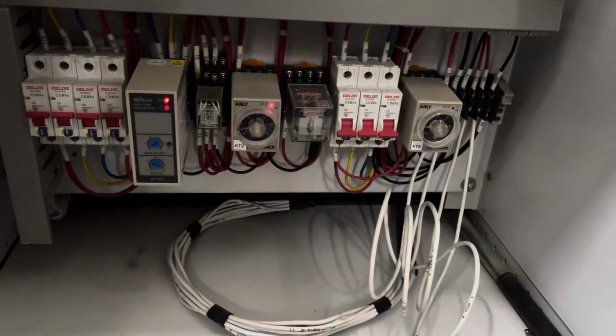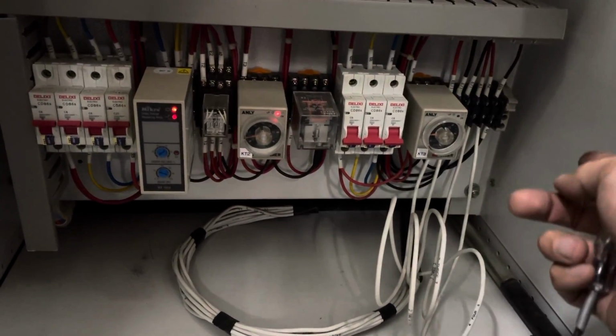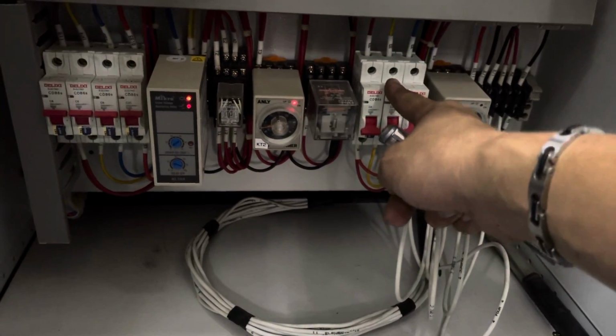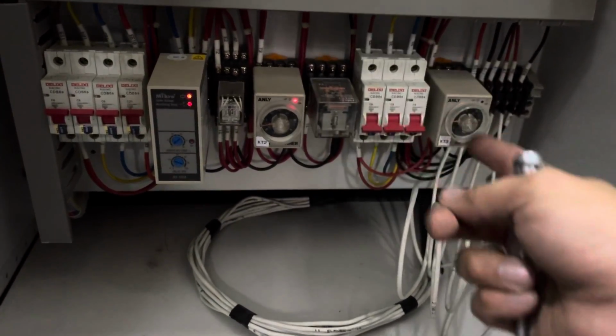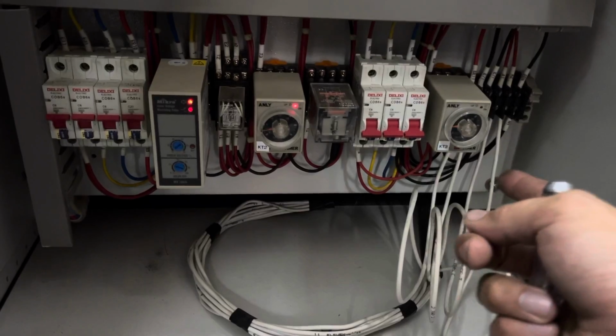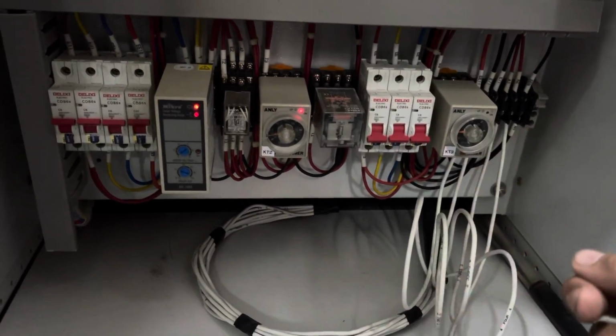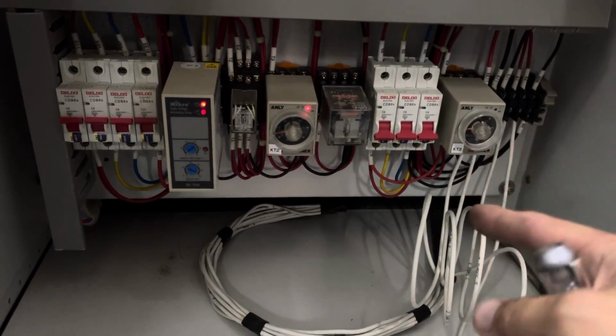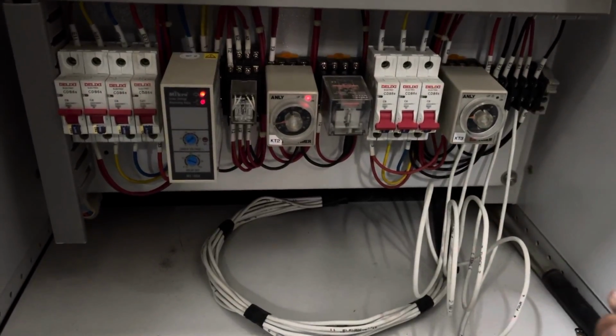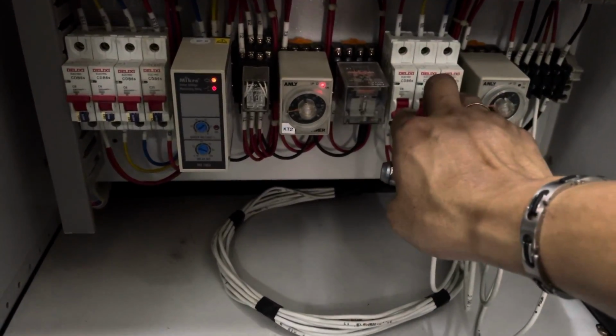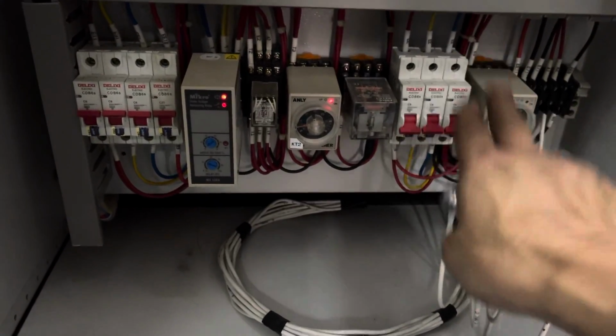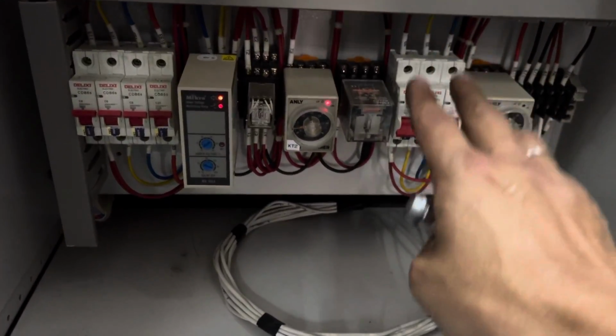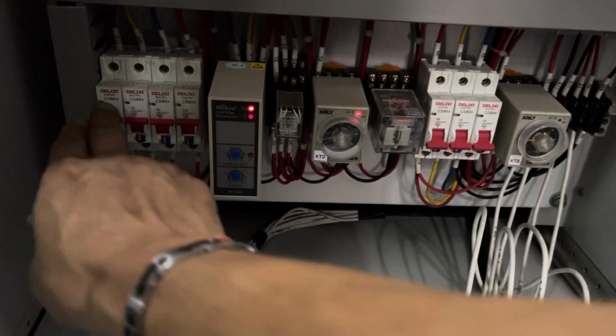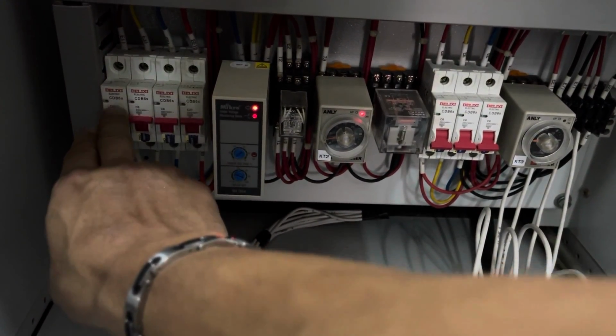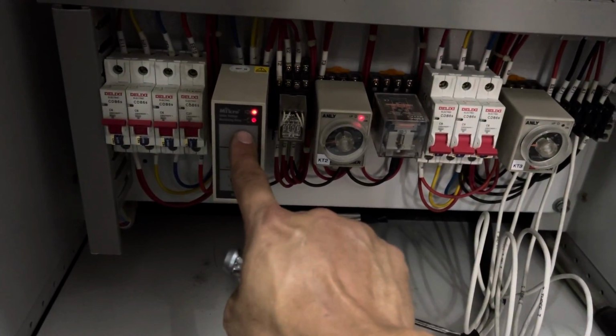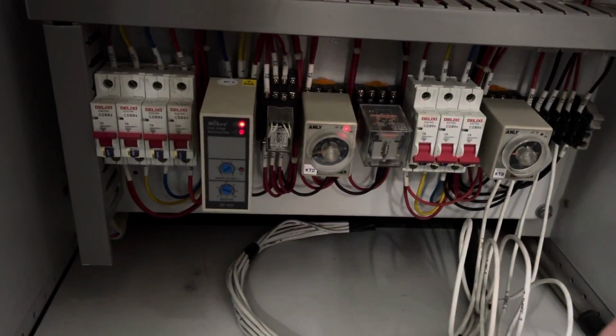This is because when the genset is running, we don't want the power supply to come back here and give power supply to the control and change over because we don't want power interruption. We just want to test the genset remotely and allow the genset to stop remotely and automatically. Okay, first step off here, genset side. Second step, off the main supply side. As I off this one, this will operate. It will call the genset to start automatically.